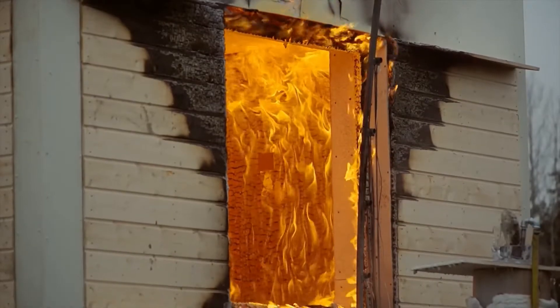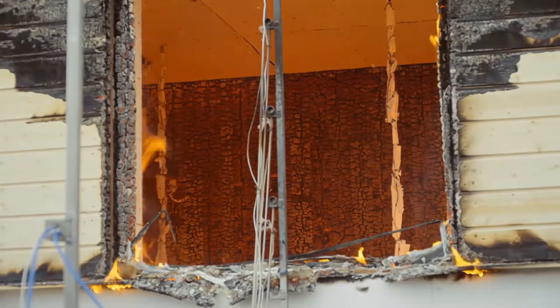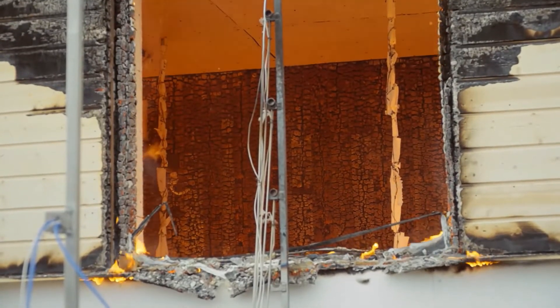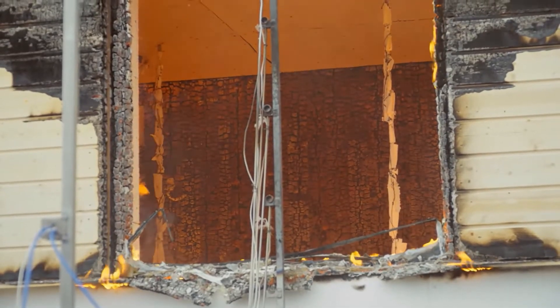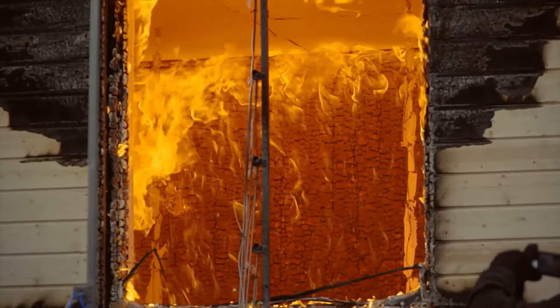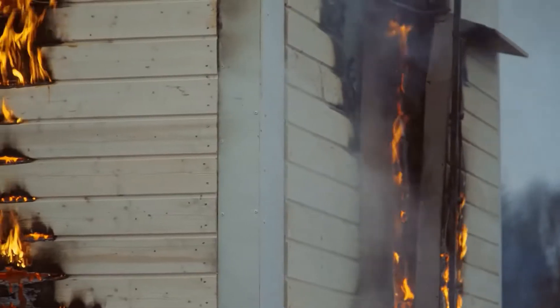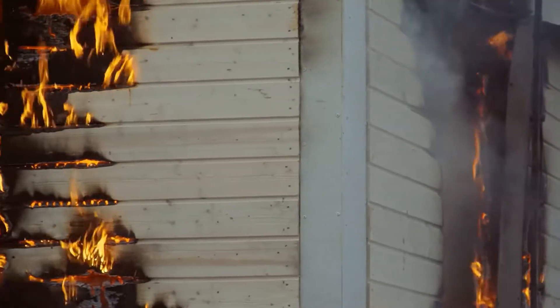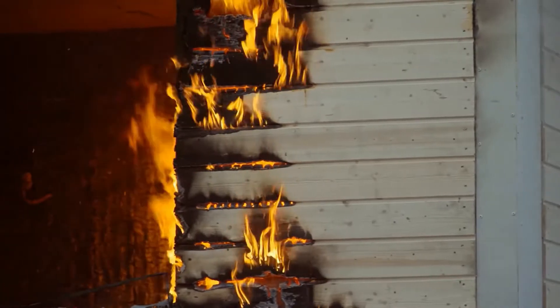The main purpose of the test is to monitor the behavior of the cross-laminated timber surfaces exposed to fire. It was expected that the first and the thickest layer of this timber would char, which in turn would protect the wooden structures, preventing the fire from spreading further. Therefore, the fire would decay and finally extinguish by itself when all the combustible materials have burnt out.